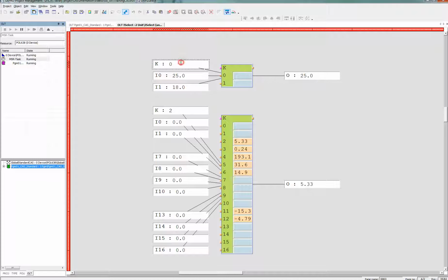So in case we are in comfort mode, the channel is 0, therefore the set point is 25. If we are in reduced temperature mode, we open channel 1 and we have value 18. It's a really nice case of graphical programming of case syntax in ST.